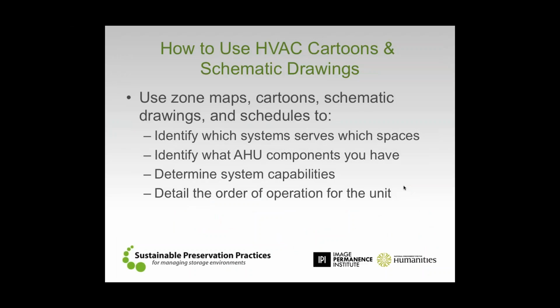We can do that using zone maps and cartoons and schematic drawings to go through and, first and foremost, identify which mechanical system is actually serving which space. Do we have situations where we have a mixed-use zone and we're trying to figure out, all right, who all receives some of this air? We want to make sure that we know what different components we have within the air handler. We talked about that a lot last month in terms of how do you identify a cooling coil or a heating coil or a filter.